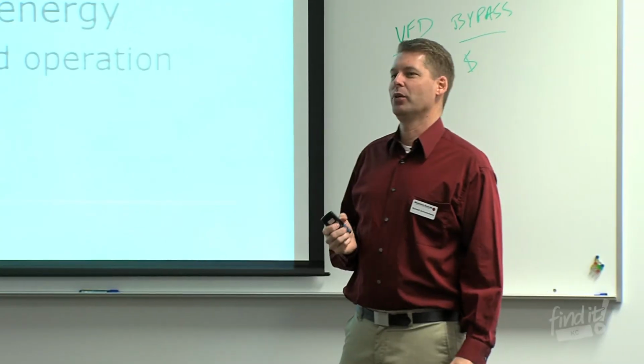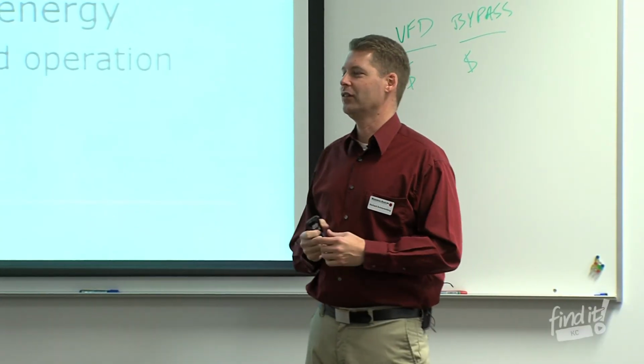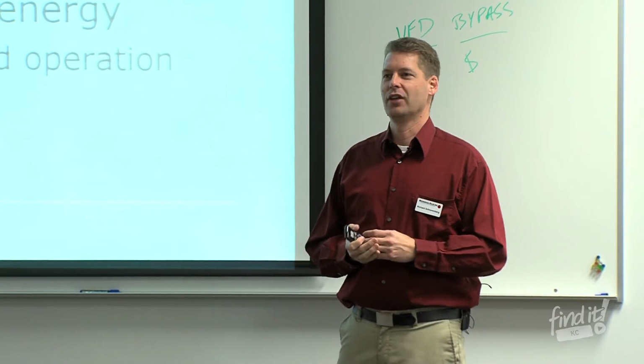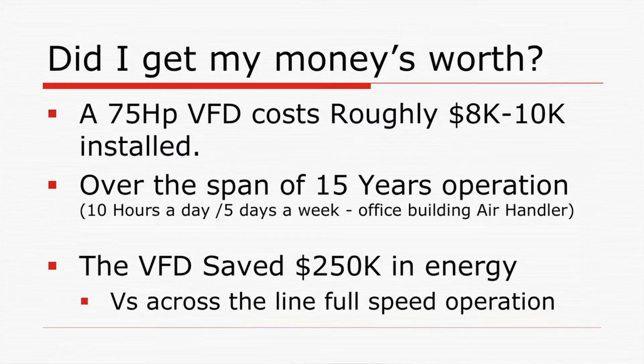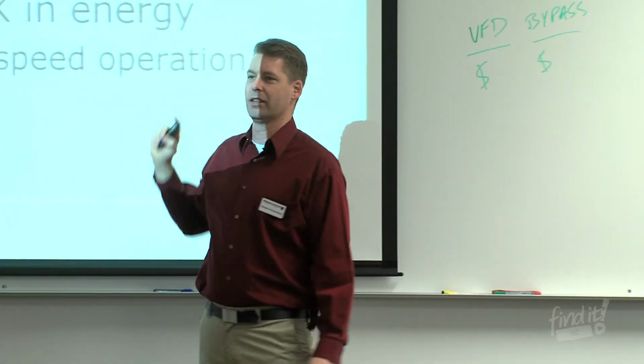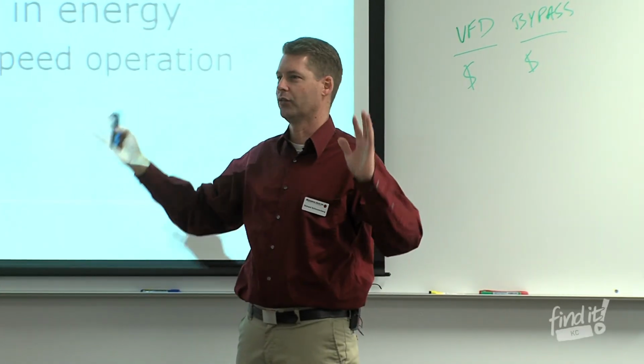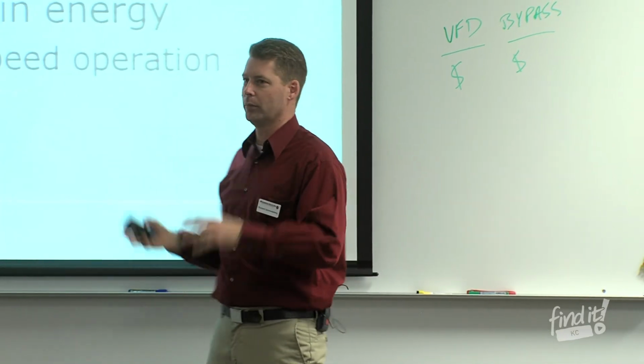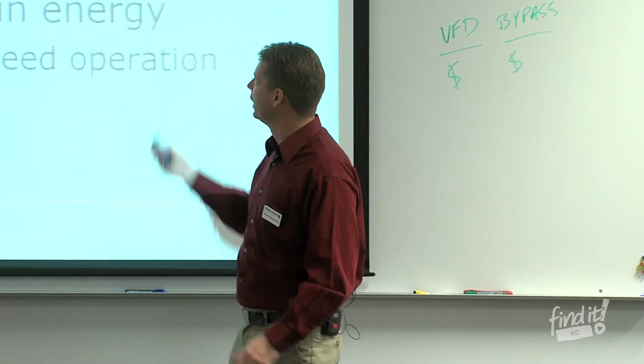But the end result is that we had to put in some calculations. What does that VFD save you? How much energy did that VFD save? How much cost has it not cost you by having a VFD? So I put a simple calculation together for, in this case, a 75 horsepower VFD. And a 75 horsepower VFD roughly costs $8,000 to $10,000 to put in.